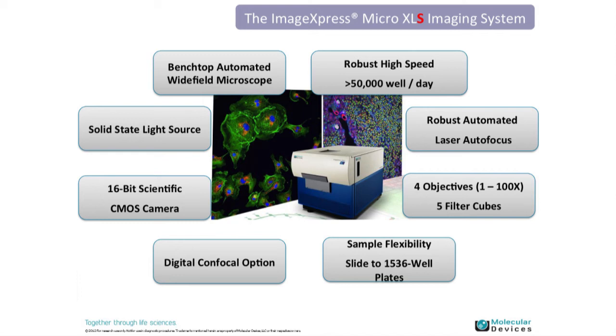A bit about the hardware. The ImageXpress Micro XLS platform is about the size of a benchtop instrument — we have an example at our booth. It was custom-engineered for speed and image quality, capable of about 50,000 wells per day depending on your application. It uses a combination of laser autofocus for plates as well as image-based autofocus for speed and flexibility. Within the system you can configure four objectives and five filter cubes.